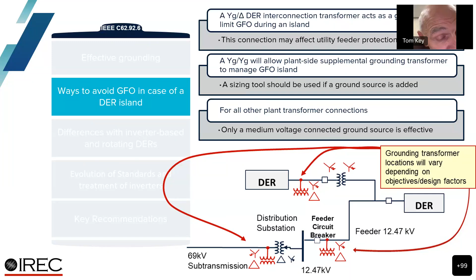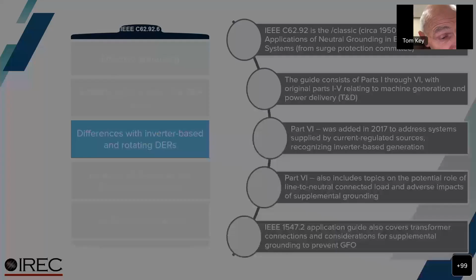The problem is if the one that's on the 69 kV, if you have a fault, you're disconnected from that one. So that's why you end up needing another one further down line in order to provide that effective grounding. I think we can go on, Brian. Or Midhat, you're the one flipping the slides?